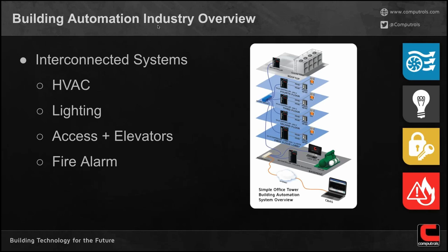We can use the building automation system to do some very cool things. We can monitor daylight, measured in a term called foot candles - the ambient window light. When the foot candles reach a certain threshold, we can say, okay, turn on the control point, the relay, and as a result the indoor lights come on. That's an example of inputs and outputs working together, all three core components coming together.